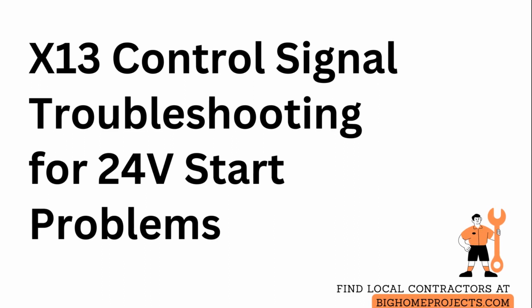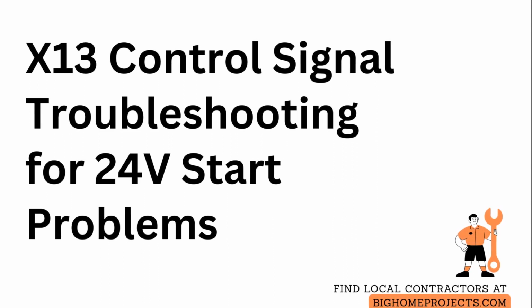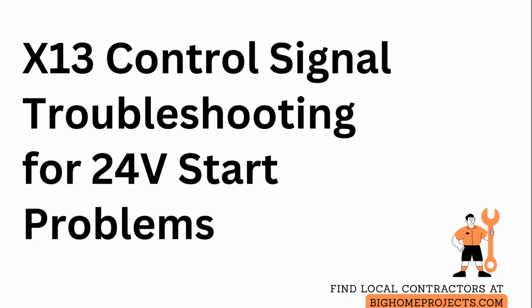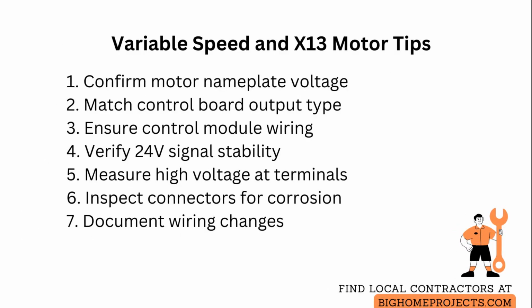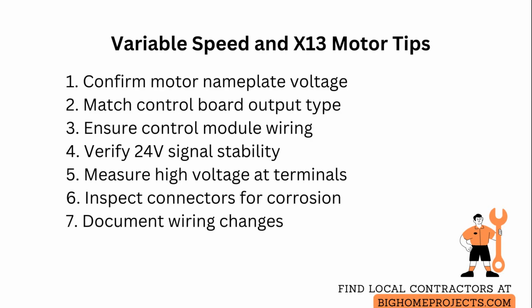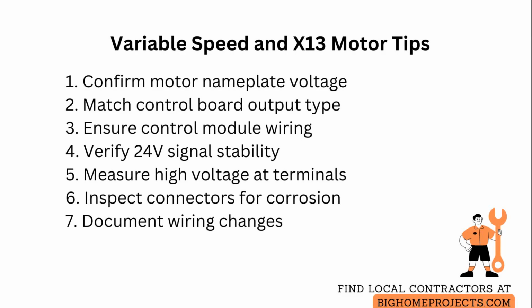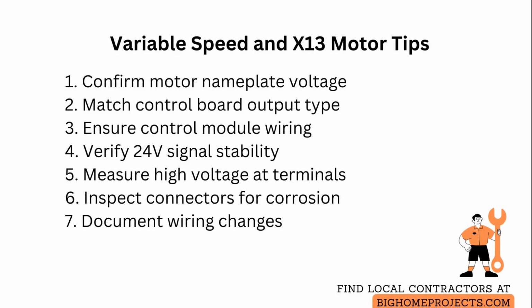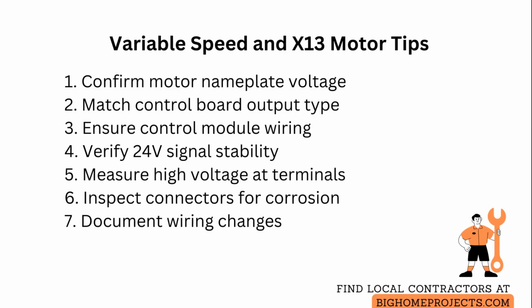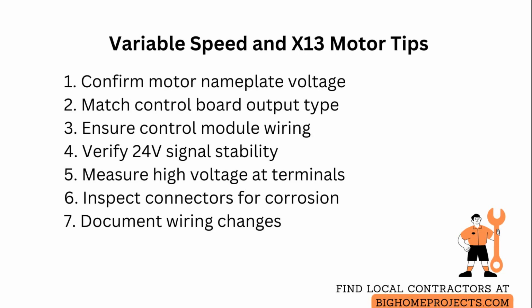Variable speed and X13 blower motors receive full high voltage power, yet only run when given a separate control signal. Variable speed motors modulate airflow by varying input frequency or voltage using an internal or external control module, so you can set fan speed precisely for comfort and efficiency. To use them, confirm the motor nameplate voltage and match the control board output type, either 24-volt alternating current or direct current control signals, and ensure the motor control module is properly wired to the thermostat or fan controller.